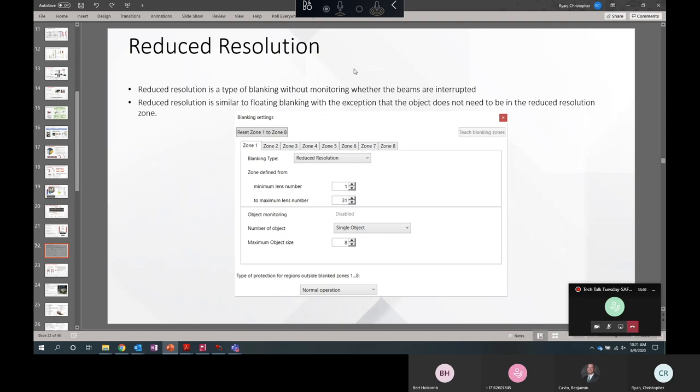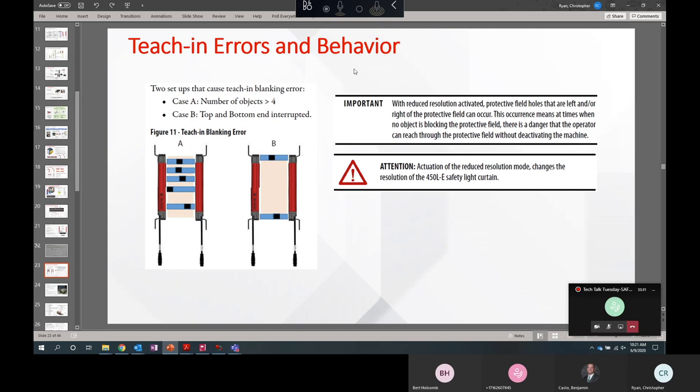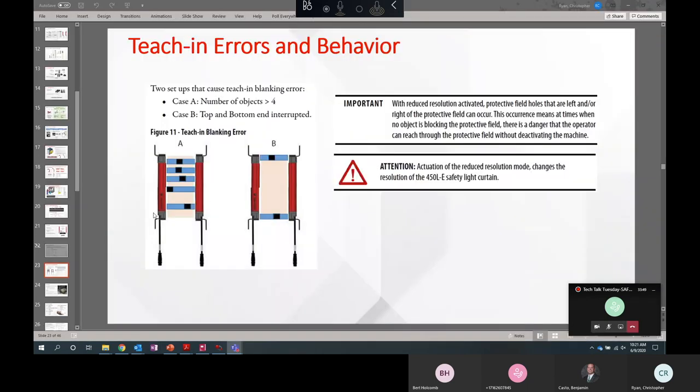And that just shows the configuration screen. A couple things to look out for. The top and the bottom are synchronization beams. So one of them must be unblocked at all times before the teach procedure can be done. You can't have more than four areas to blank at once. You can't teach more than four areas to blank at once. You can do it in the software configuration. And another note, activating reduced resolution changes the resolution of the light curtain. So just think about that if your machine risk assessment calls for a specific resolution at a certain distance from the hazard.